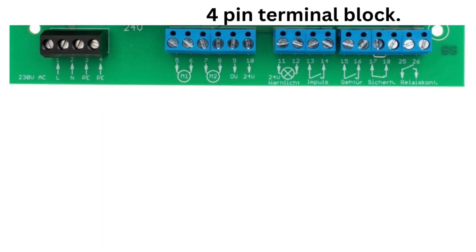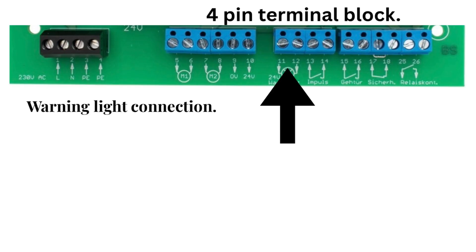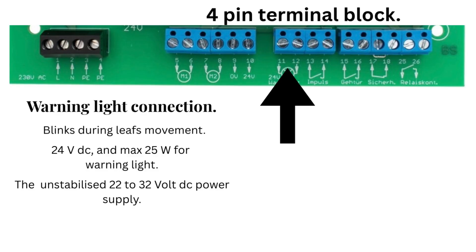4-pin terminal block. Terminal 11 and terminal 12. Warning light connection. Blinks during leaf's movement. Terminals 11 and 12 output plus 24 volt DC and max 25 watts for warning light. The unstabilized 22 to 32 volt DC power supply.